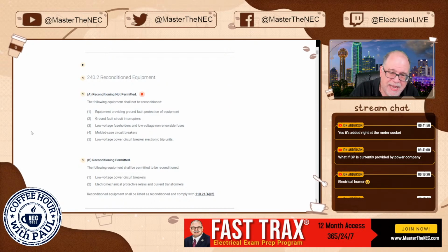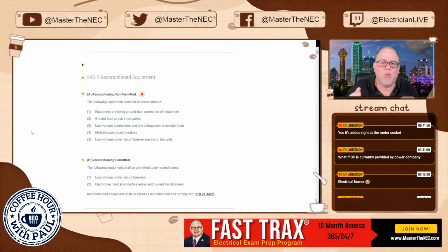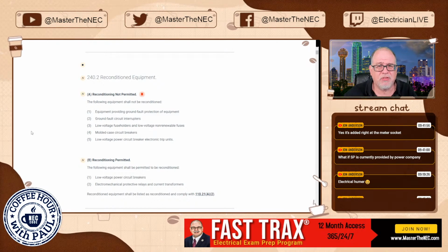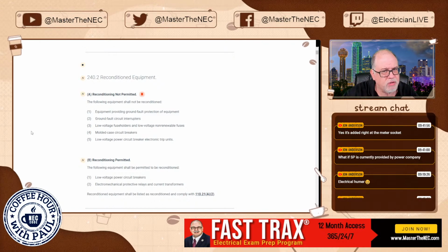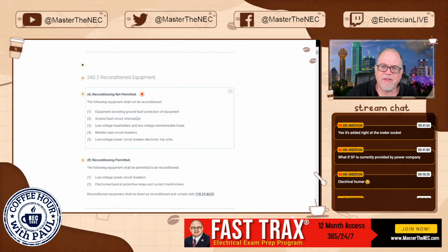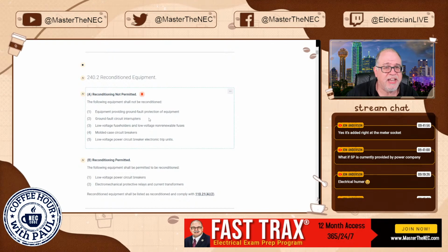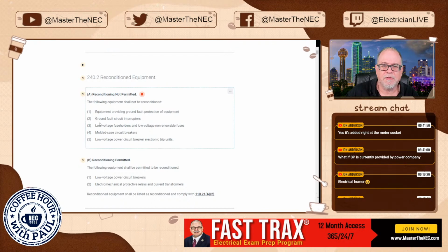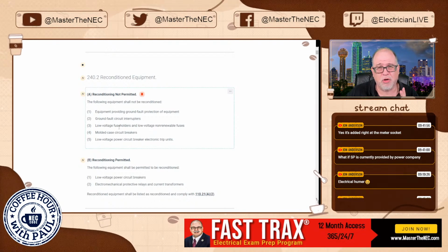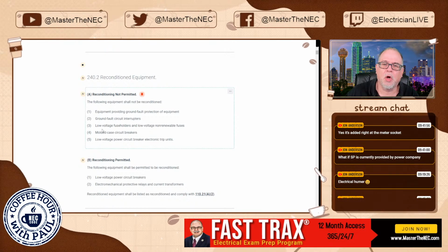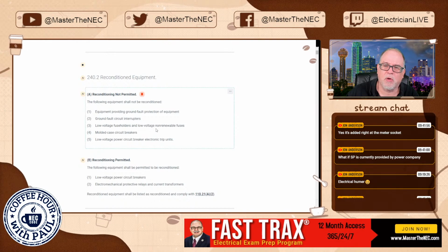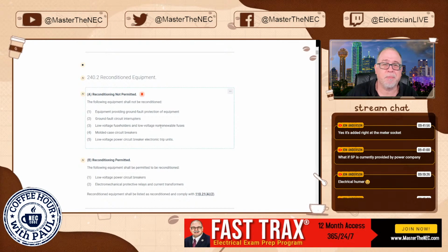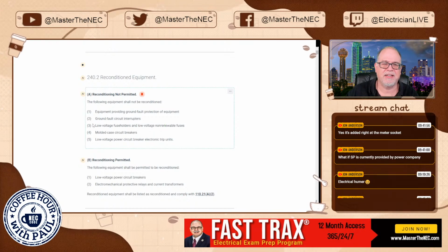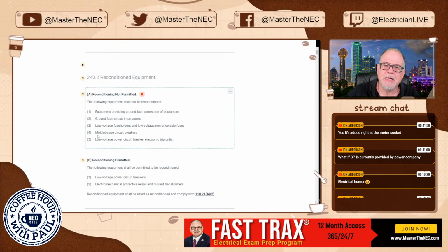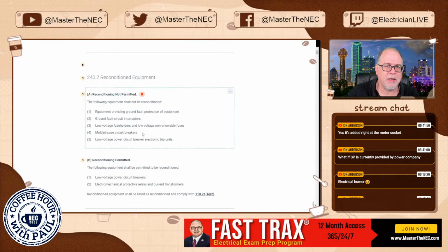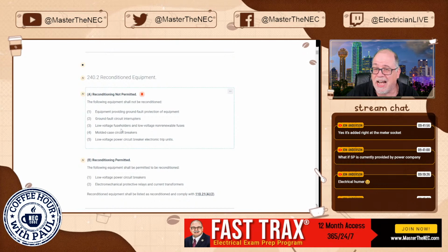And I like this format now. What's permitted to be reconditioned and what is not when it comes to 240. And what is 240? Overcurrent protection. So equipment providing ground fault protection of equipment, so that's GFP, it is not reconditionable. Ground fault circuit interrupters, no brainer. All that circuitry in there, not reconditionable. Low voltage fuse holders and low voltage non-renewable fuses. Again, a lot of that's paper or cardboard backed. Obviously, you wouldn't reuse those, recondition those. Molded case circuit breakers, you know, those 15, 20 amp small molded case circuit breakers, not reusable.